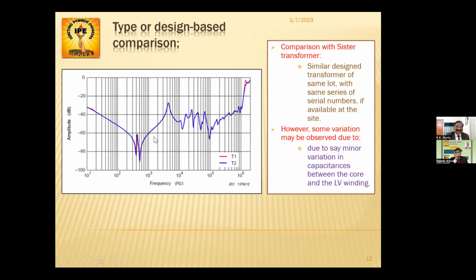Then comes the comparison with a sister transformer. T1 is one transformer and T2 is the sister transformer, but they may not be similar because of minor variations in capacitances between the core and the LV winding. Sister transformers must have been manufactured under the same design, but while manufacturing there could be minor variations in capacitance between the core and LV winding, and HV winding to LV winding as well.